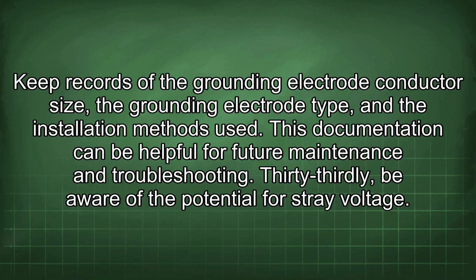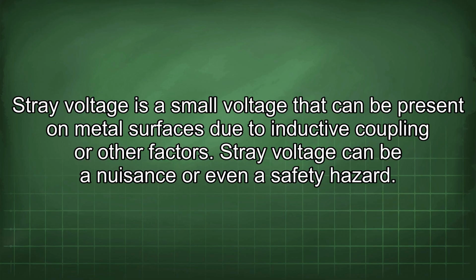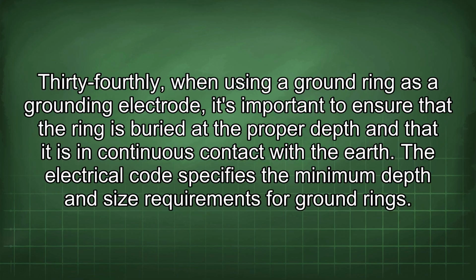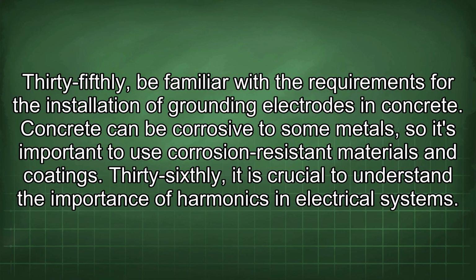33rdly, be aware of the potential for stray voltage. Stray voltage is a small voltage that can be present on metal surfaces due to inductive coupling or other factors. Stray voltage can be a nuisance or even a safety hazard. 34thly, when using a ground ring as a grounding electrode, it's important to ensure that the ring is buried at the proper depth and that it is in continuous contact with the earth. The electrical code specifies the minimum depth and size requirements for ground rings. 35thly, be familiar with the requirements for the installation of grounding electrodes in concrete. Concrete can be corrosive to some metals, so it's important to use corrosion-resistant materials and coatings.